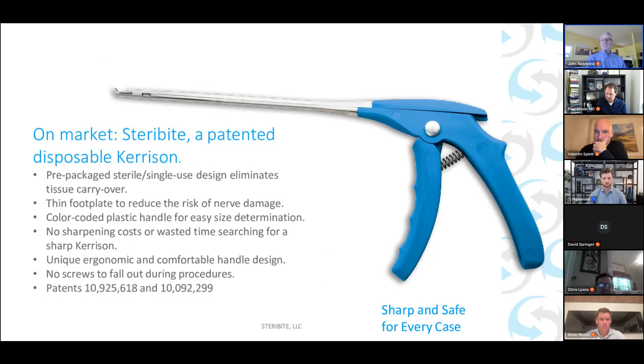When we decided to develop this product, we said, what are the problems with existing Kerrisons? And I touched on this a little bit. First of all, there's usually screws on Kerrisons that become loose. So we eliminated the screw. The spring on a Kerrison has 2 screws and a leaf spring that can catch a surgeon's glove. The screws can break and fall out. So we recessed the spring. We wanted to make the handle a little bit more comfortable for the surgeon. And we took the spur off the back here. If a surgeon flips it upside down, they don't have that sharp spur sticking in their hand. And we made it a thin foot plate. So it's actually a better product.